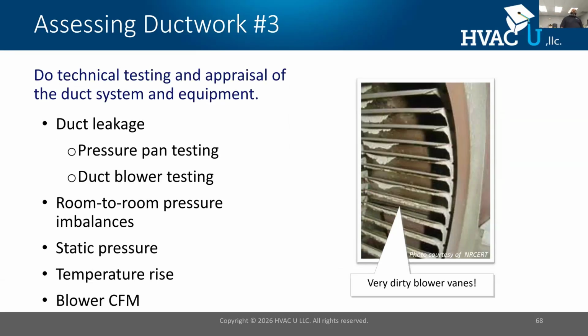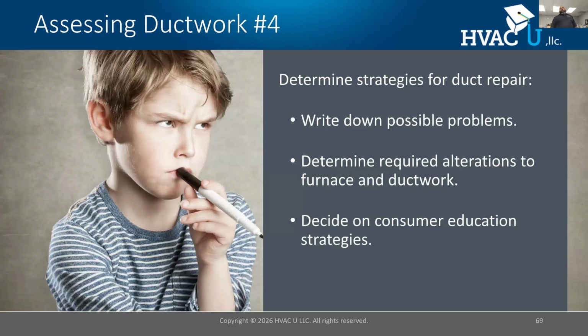Here's the big six. Duct leakage, room to room pressure, static pressure, temperature rise, blower, and not to mention direct airflow measurements. If we use these tools, we can evaluate any duct system and any problem. They're going to fall into these issues. And with that, we'll wrap it up.